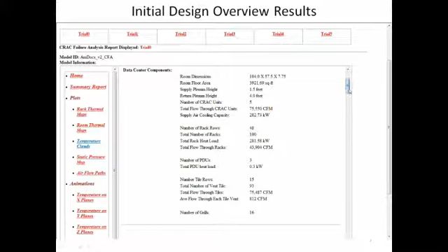You see here that the units aren't pulling much heat out. They're pulling 50 kW out each, a little over 10 tons. They're 30-ton CRACs pulling 10 tons out a piece?